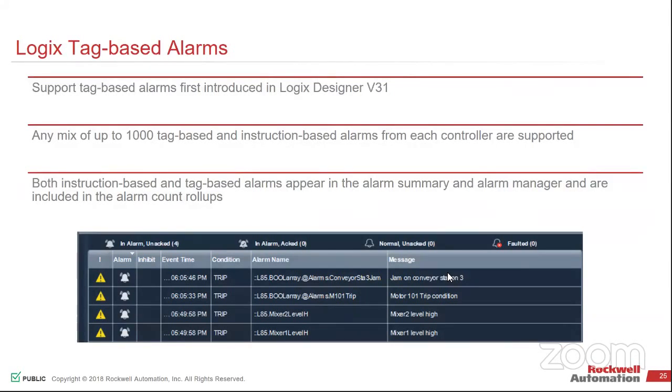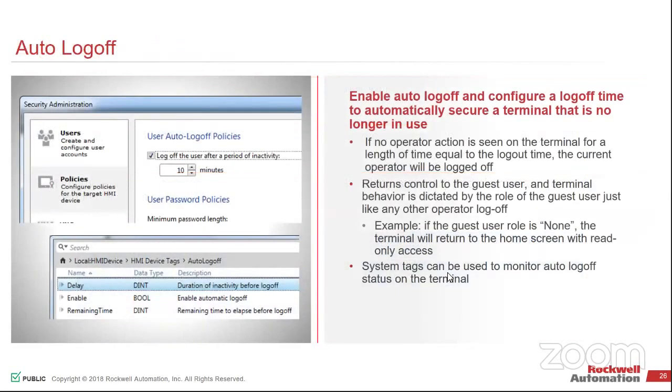And setting up the tags is going to be a whole lot easier with this. The diagnostic page has already been created for you. The alarm page and the banners are already done and configured, ready to go. And more importantly, we have an auto log off function. If David was excited about his tiny little change in Studio 5000, I'm excited about auto log off. You can have it tied to actual tags, where the policy is that after someone touches it, it will turn off after 10 minutes or 5 minutes or whatever. That can actually be set up in a tag type situation now.